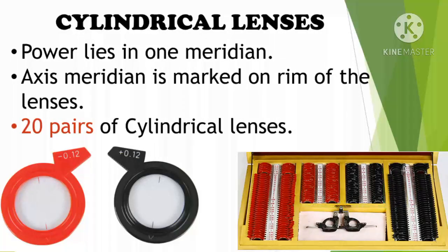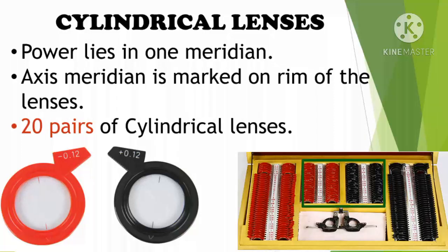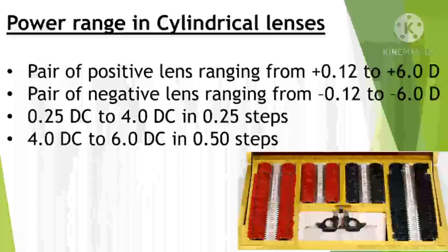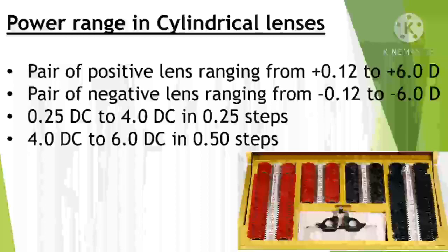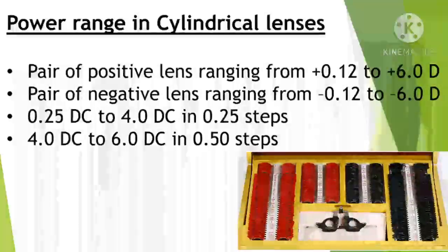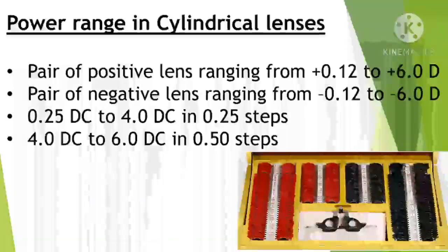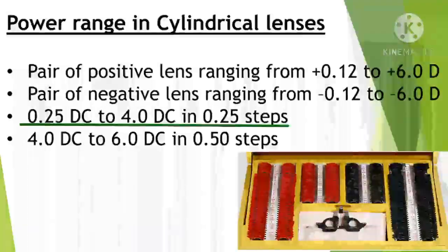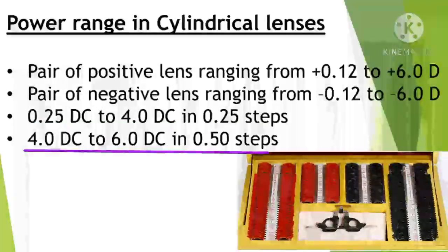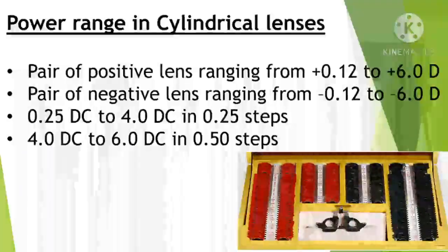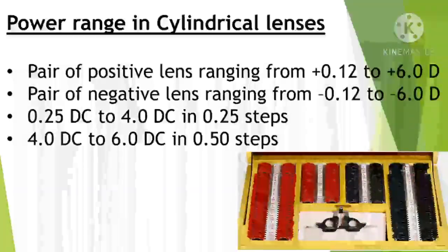Cylindrical lenses have power in only one meridian; unlike spherical lenses, the power is not the same in each meridian. On every cylindrical lens, the axis is marked. There are a total of 20 pairs of positive and 20 pairs of negative cylindrical lenses in the trial box. The power range of cylindrical lenses is 0.12 D to 6 D. From 0.25 D to 4 D the steps are 0.25 D apart, and from 4 D to 6 D the steps are 0.50 D apart. Cylindrical lenses are used for astigmatic correction.